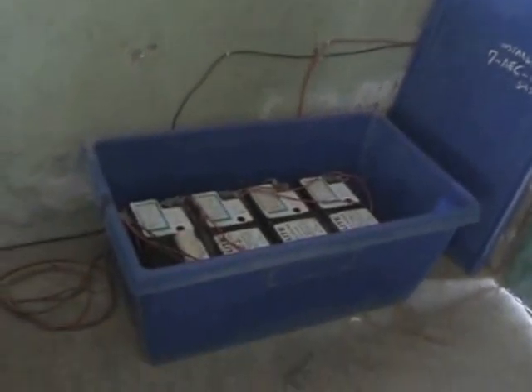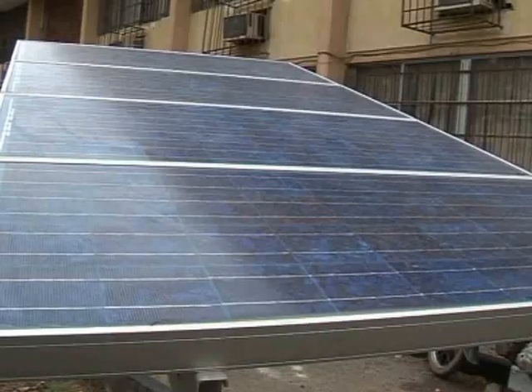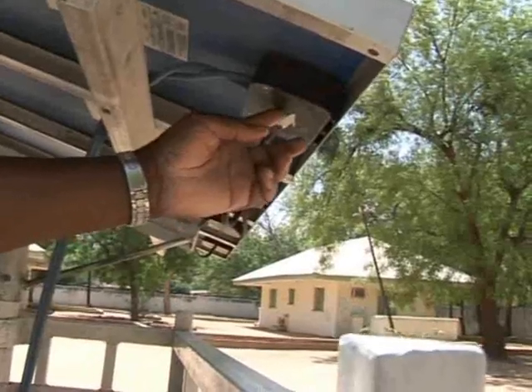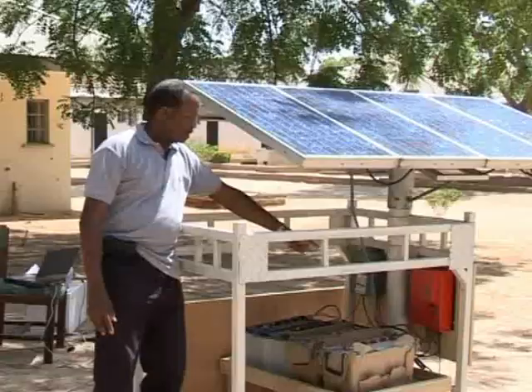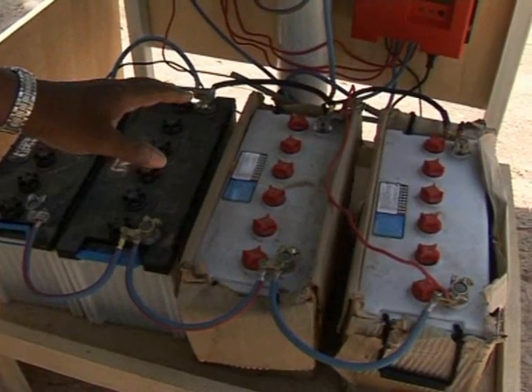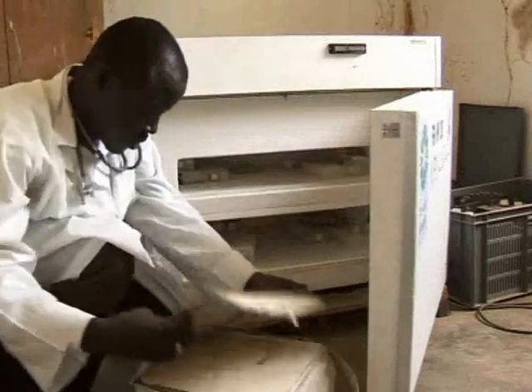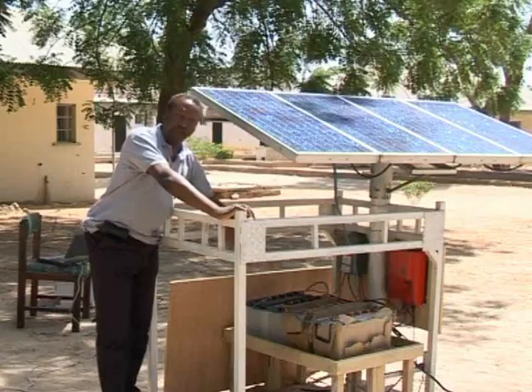So far, KXN Nigeria has installed 165 solar charging systems. The sunlight shines on the solar panels, and the panel converts the light intensity into electricity, which passes through the array cable to the controller and charges the batteries. So you can use this even when the sun's gone down overnight. Typically, we run the solar vaccine fridges from a DC current, 24 hours a day, non-stop.